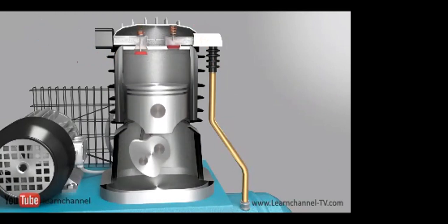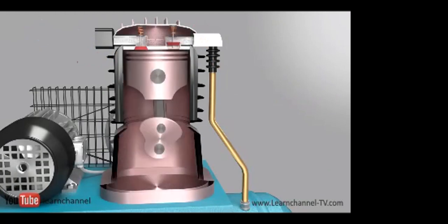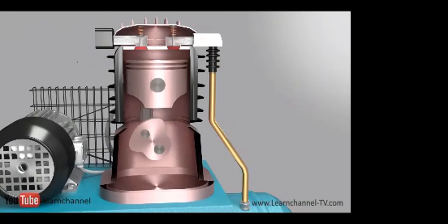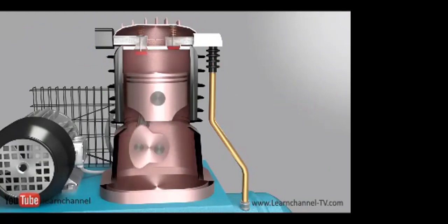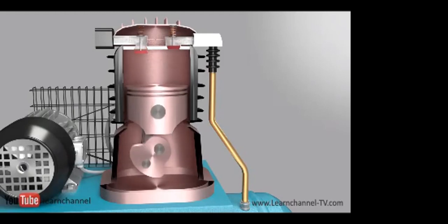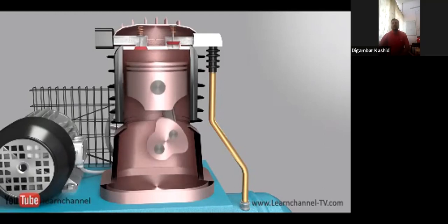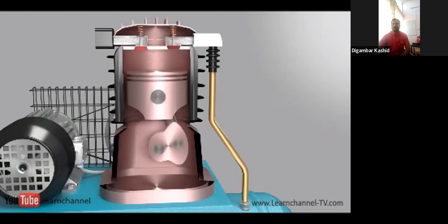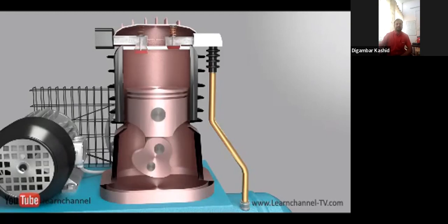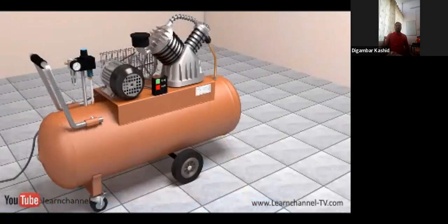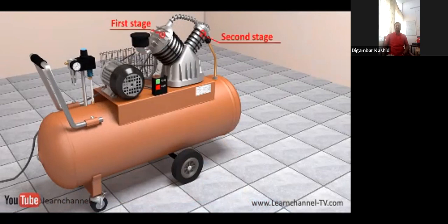Air heats up when it is compressed. This is a problem of each compressor. The result is not only a less efficient compression cycle, but also a real danger of explosion if any inflammable substances, such as oil or lubricant, come in contact with the overheated air and piston. Therefore, the compression of a single-stage compressor is limited to an output pressure of about 10 bars, or 145 psi. To achieve higher pressures, you would use a multi-stage compressor.